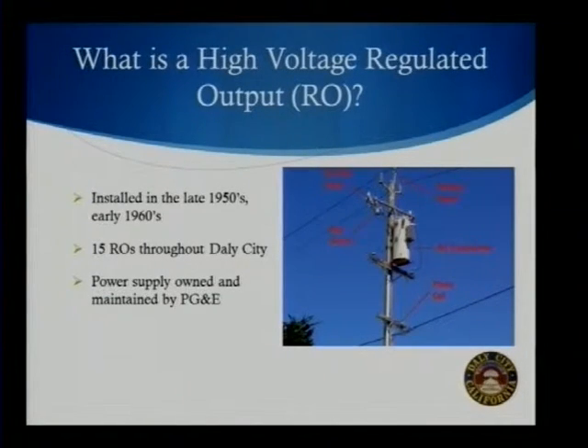It's about three times bigger than what you'd normally see in your neighborhood for a step-down transformer that takes the PG&E primary voltage, usually in thousands of volts, down to hundreds of volts before it comes into your house. This thing kind of does the same thing, but basically it maintains a constant amperage by regulating the voltage, and that voltage is very high. It uses the primary voltage, the 5,000, 4,000 volt primary voltage that's in the very top lines on the PG&E pole.